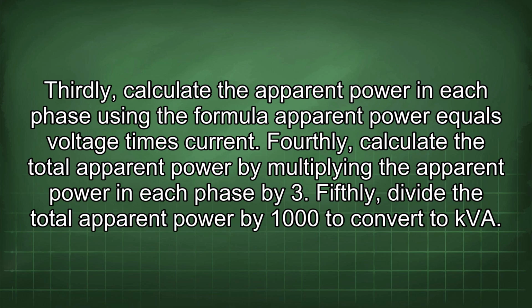Thirdly, calculate the apparent power in each phase using the formula apparent power equals voltage times current. Fourthly, calculate the total apparent power by multiplying the apparent power in each phase by 3. Fifthly, divide the total apparent power by 1000 to convert to kVA.